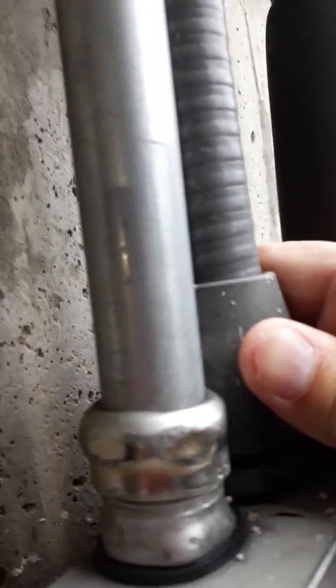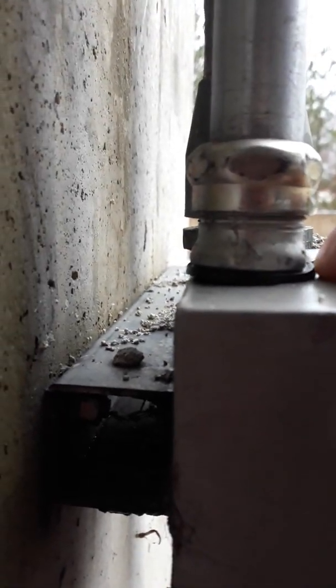What I think is happening is this is probably not tight enough up here — one of these isn't. They probably just hand tightened it. And notice there's no silicone right down there, and that's not squished — that should be somewhat squished. So that seal is starting to break down a little bit as well.